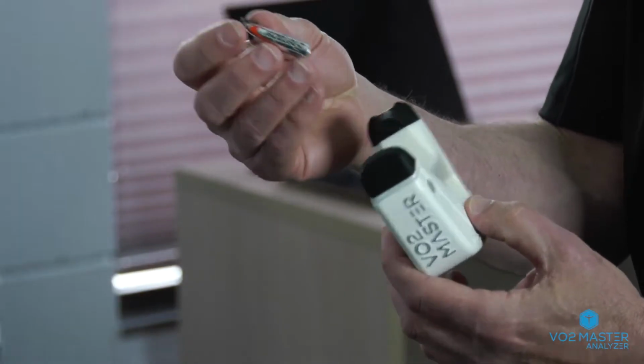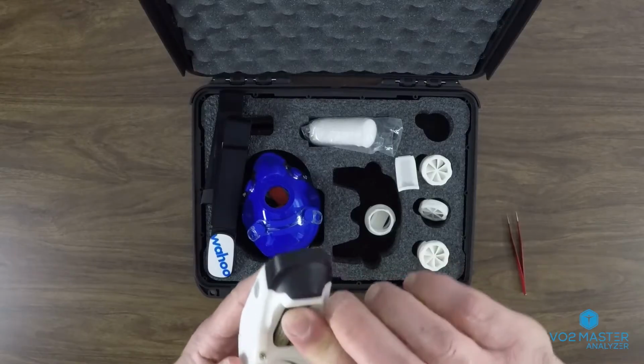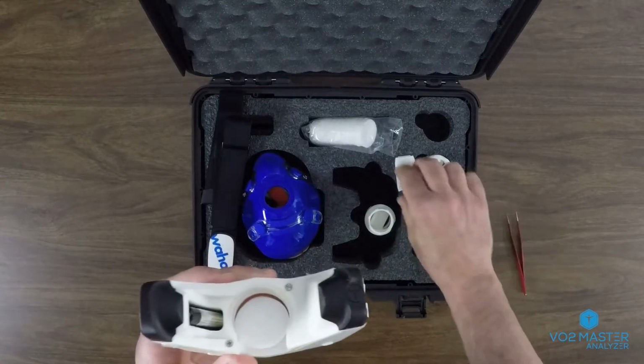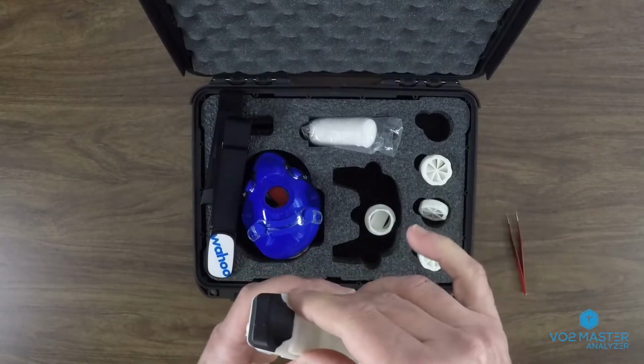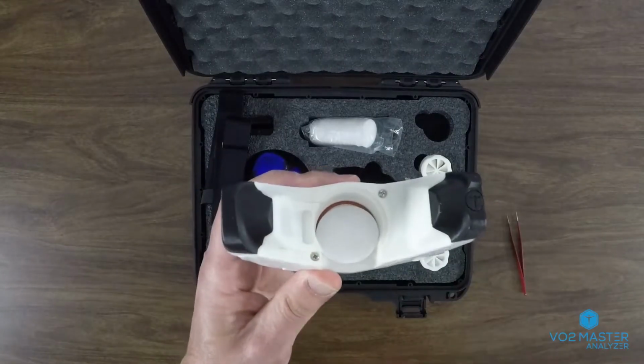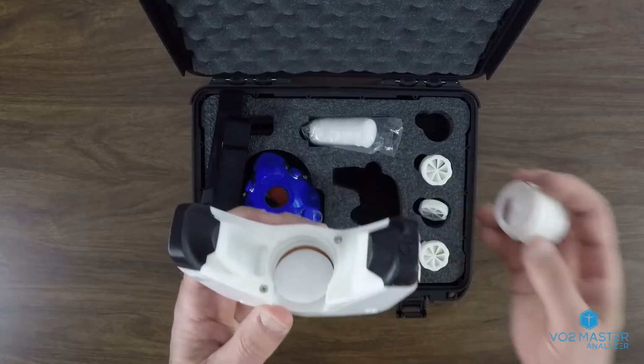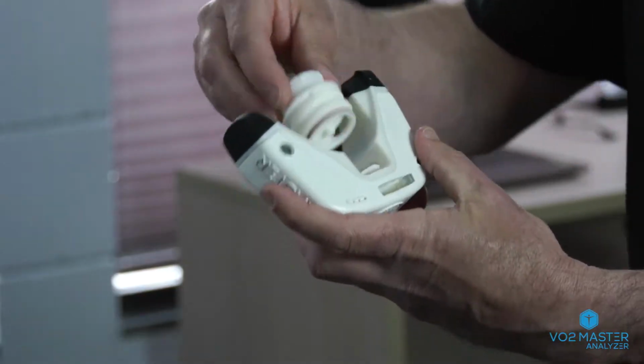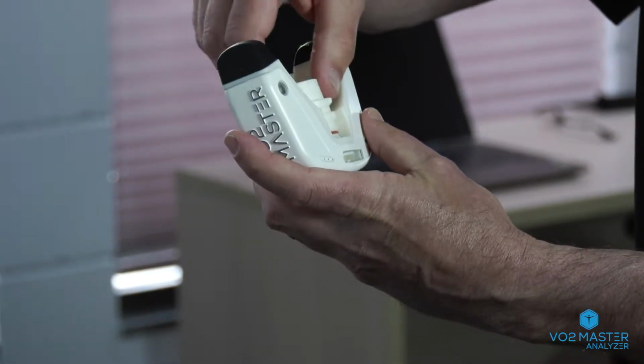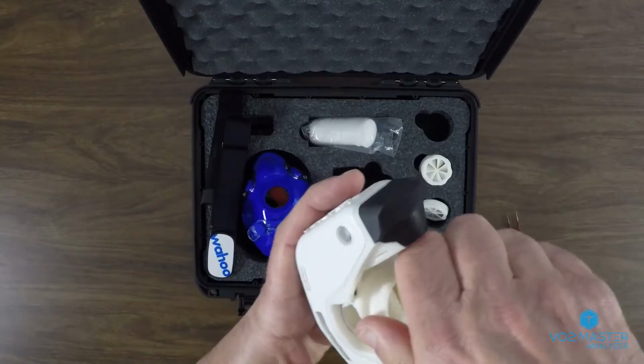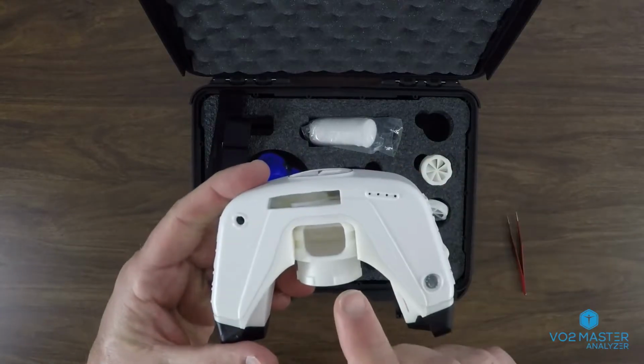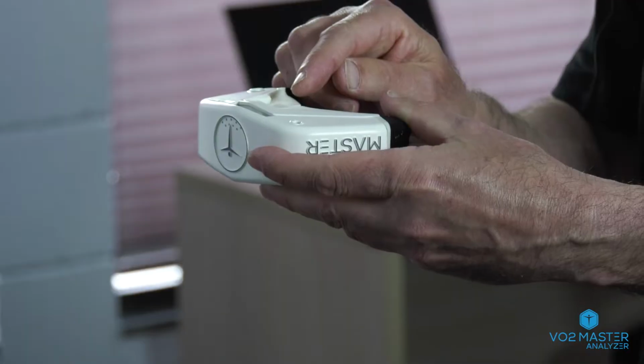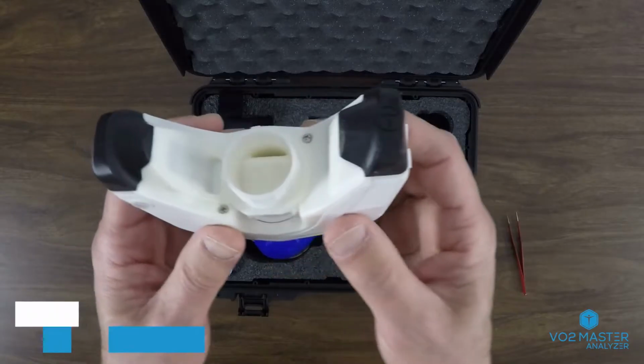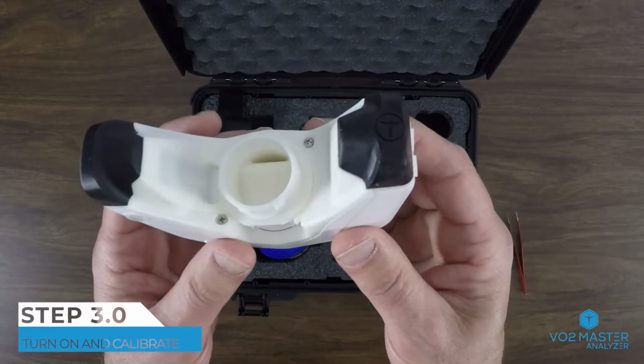Next, take a new AAA battery and insert it, and then the battery door. Note that the battery door will not stay in place until the user piece has been screwed in. So next, screw the user piece in until it stops at the bottom and can go no further. Notice the opening in the user piece is in the middle of the opening of the analyzer. With the user piece installed, you're ready to place the analyzer on the mask.